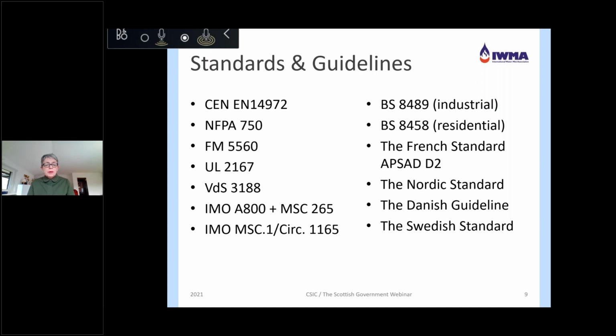Talking about maintenance, uniform maintenance routines are applied throughout the water mist industry. Maintenance requirements for water mist systems are comparable to conventional sprinkler or gas extinguishing systems. I would like to mention the matrix, which can be found on the IWMA webpage. It is a chart containing all current water mist applications and associated fire test protocols that have been published by certification or test agencies.